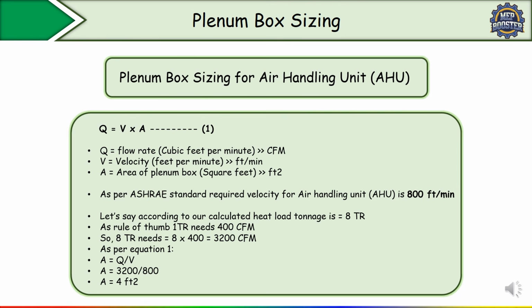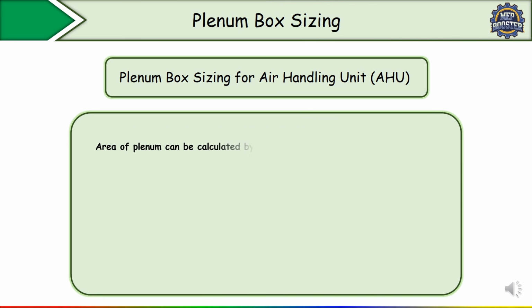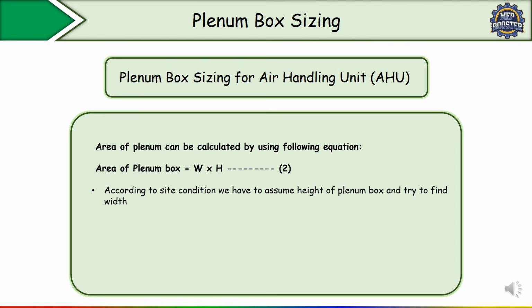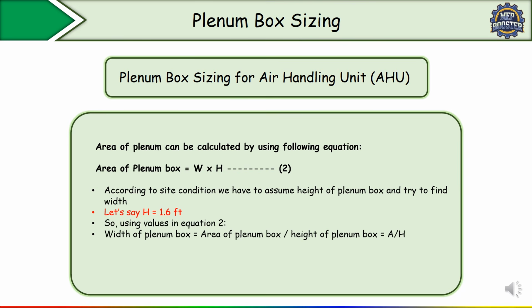Once you get the area, the next thing: the area of the plenum box can be calculated by using the following equation. All of you know, area of plenum box is equal to width into height. So this is your equation number 2. Now, according to site condition, we have to assume the height of the plenum box and try to find the width. Suppose let's say the height is 1.6 feet, correct? When you substitute this height value in equation number 2, you will get the width.